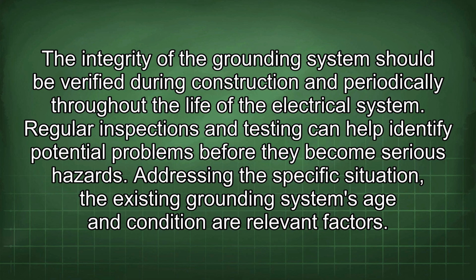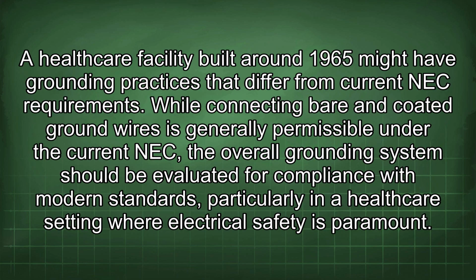Addressing a specific situation, the existing grounding system's age and condition are relevant factors. A healthcare facility built around 1965 might have grounding practices that differ from current NEC requirements. While connecting bare and coated ground wires is generally permissible under the current NEC, the overall grounding system should be evaluated for compliance with modern standards, particularly in a healthcare setting where electrical safety is paramount.